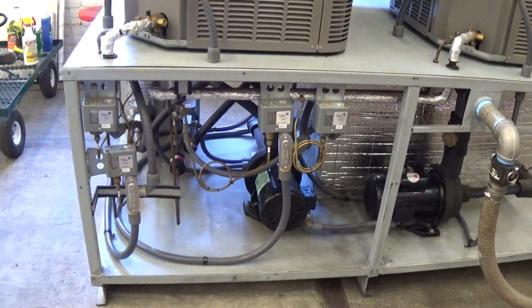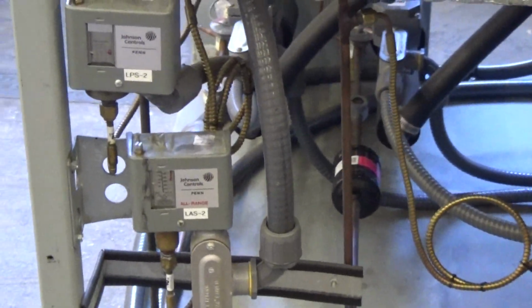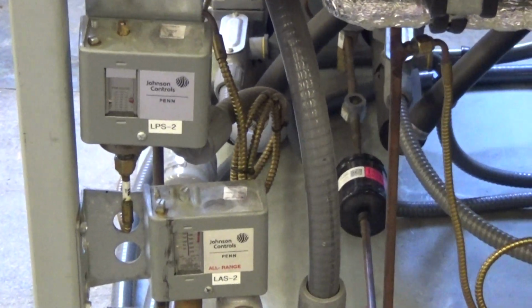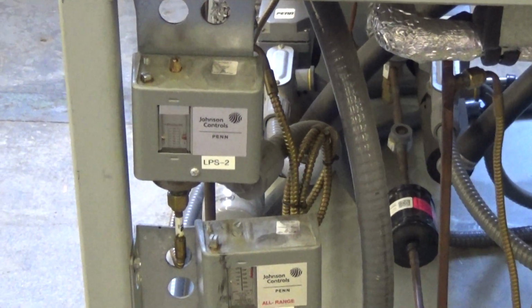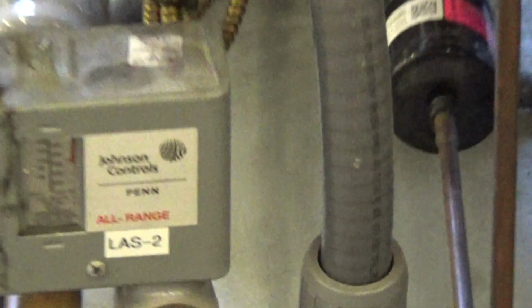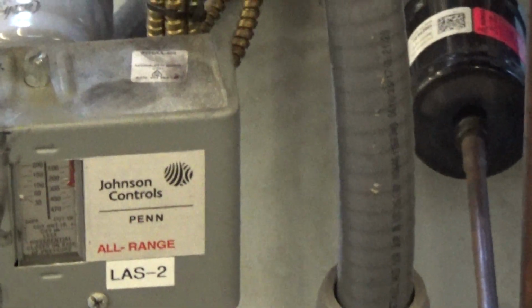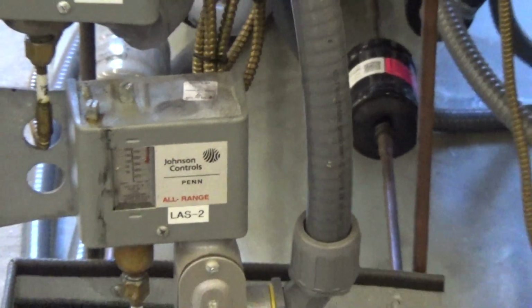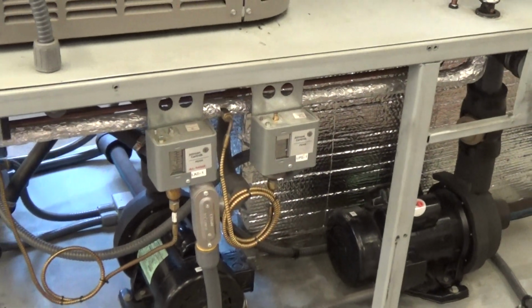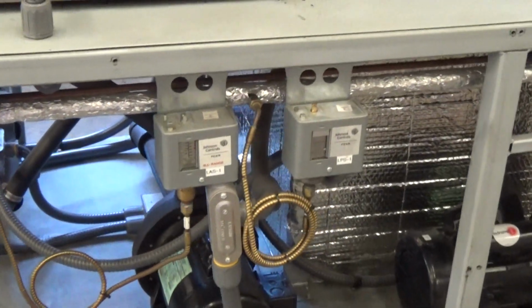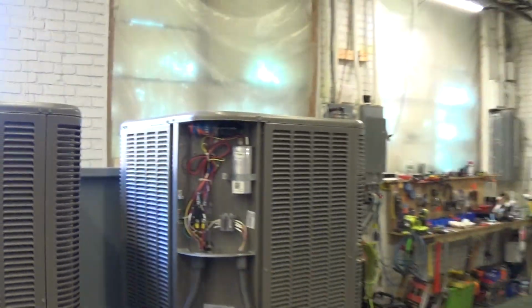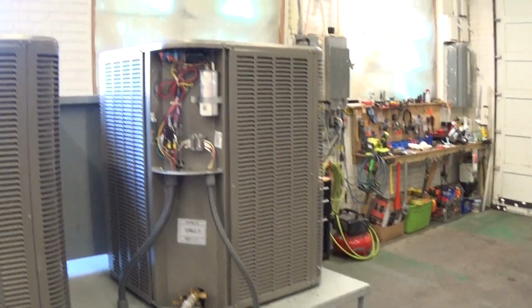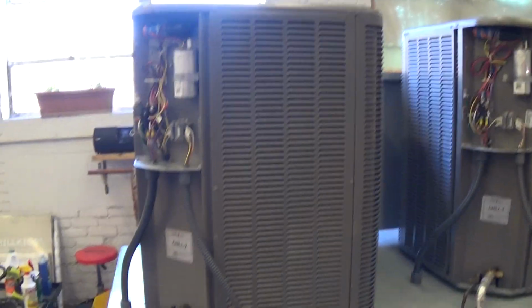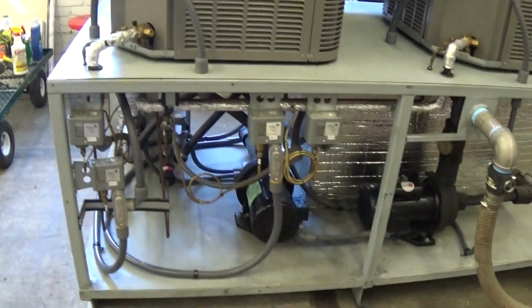While we're here on the back of the chiller, for each circuit, we have a low pressure adjustable switch, and then we also have the LAS switch for each circuit, which is low ambient or fan cycling. And really no need to touch those. An HVAC contractor may want to adjust a little bit out in the field if it's super cold. But the switching of those fans at different temperatures or pressures is one of the things that allows this thing to run outdoors in colder weather in the Northeast, as this one is.